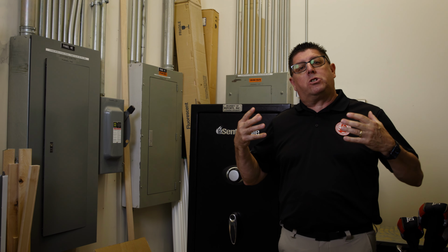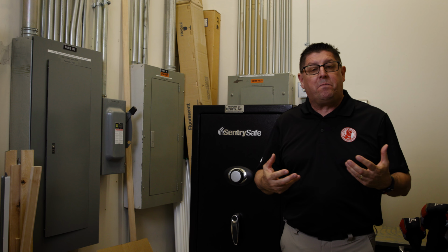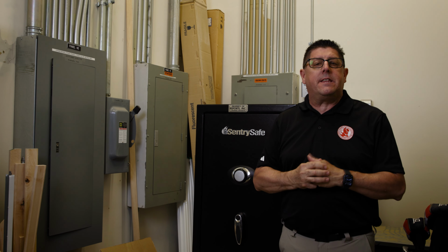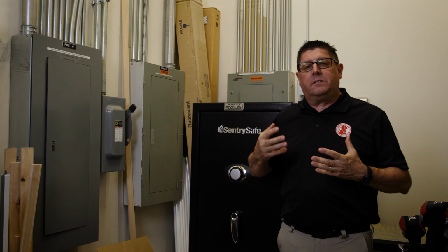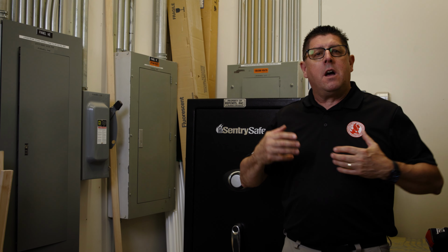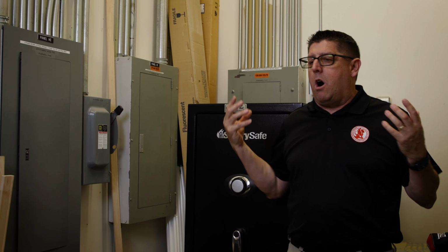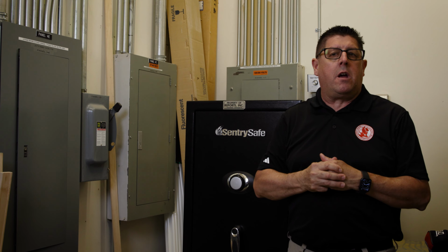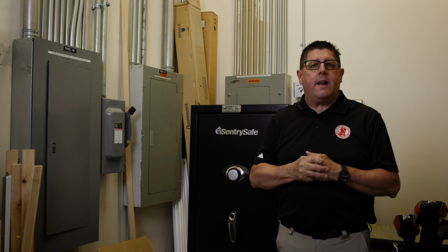And then when we come into general storage rooms, like this electric room that we're in today, we can't have anything stored in this room that's not part of that electric system. So gun safes, golf clubs, light bulbs, boxes, none of that should be in this room. I should be able to have access to all of these pieces of electric without being encumbered by anything like stored items.